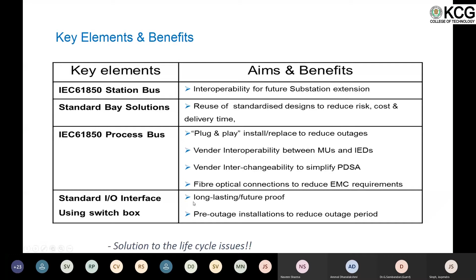One thing we considered while designing those things as a protection system, because I was mostly associated with 400 kV substation grades, 400 meaning EHV grades, where tripping time is very critical. We need to trip the circuit within 80 milliseconds or so that there will not be any grid disturbance and the grid can survive. So all tripping signals shall be received by the breaker within 10 milliseconds excluding inter-trips, and that is a 10 millisecond timing from the control system and protection system to the breaker. That was practice in India as well as in UK as well as other utilities.